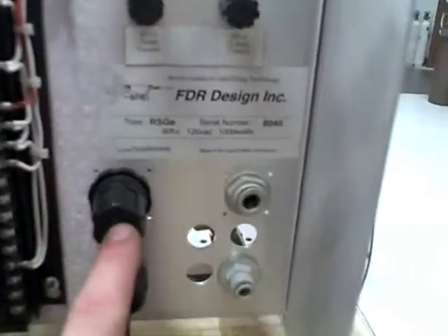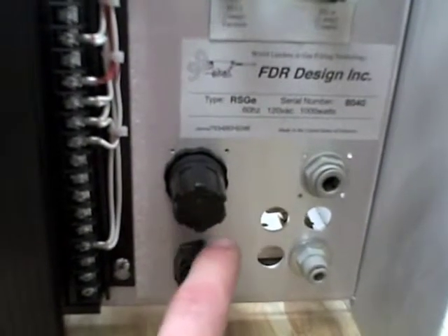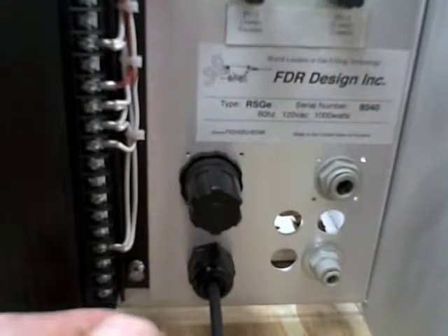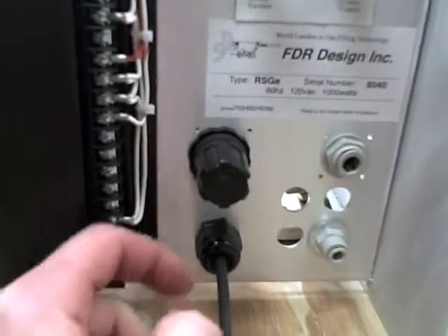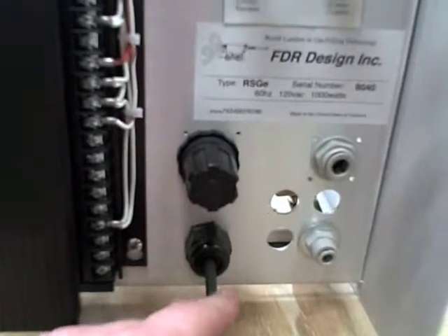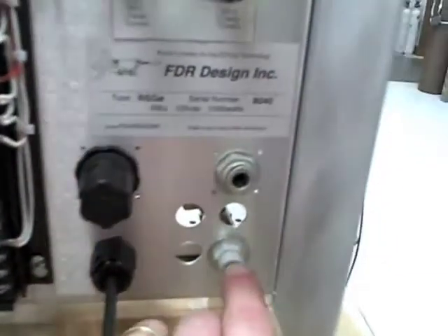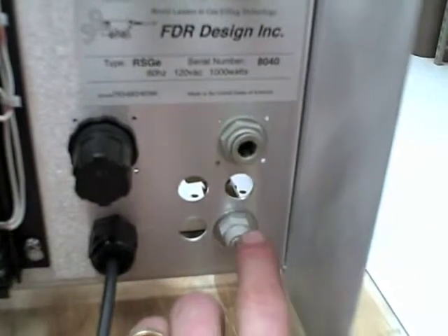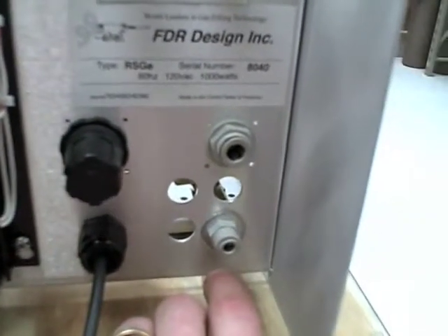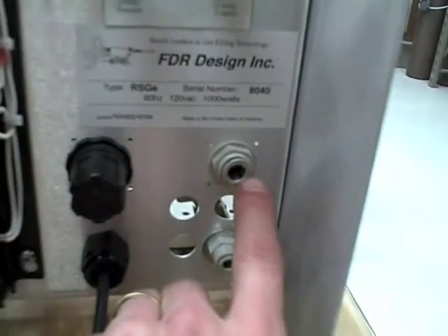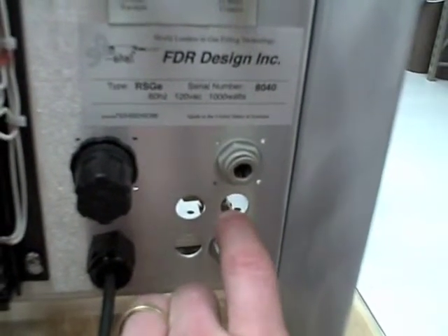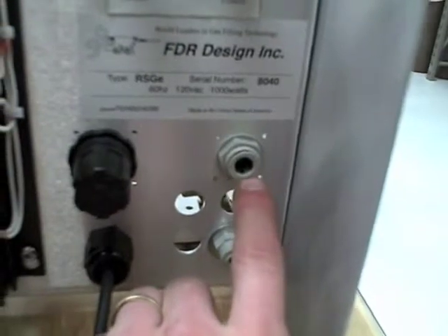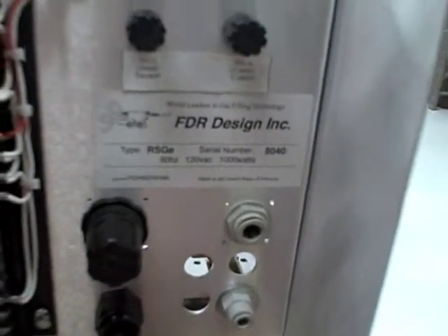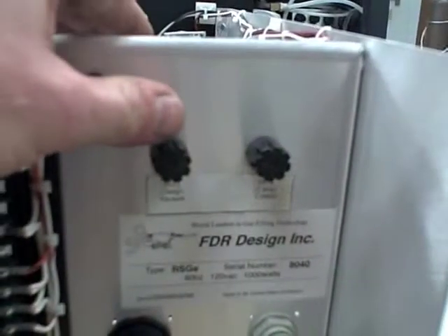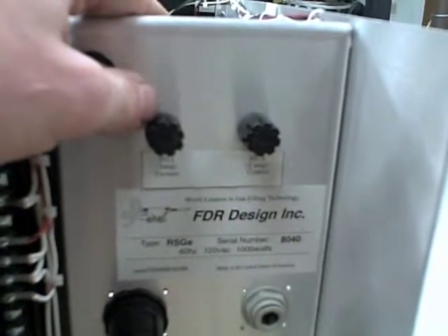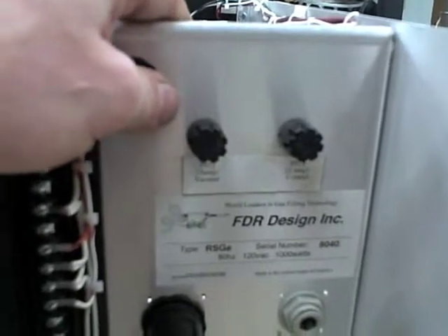If we move over, we'll see the argon regulator, and this is going to regulate how much argon is actually going out of the filling lance, and so we'll want to turn this up or down. As we're doing the calibration, we'll go through that. This is going to be the argon inlet, so I'll connect our argon to that, and then this is just a vacuum vent, so as the gas comes through the vacuum pump, it just comes out of this, just to vent into the atmosphere. And then up here we'll have the fuses, and they're just standard glass bus type fuses.